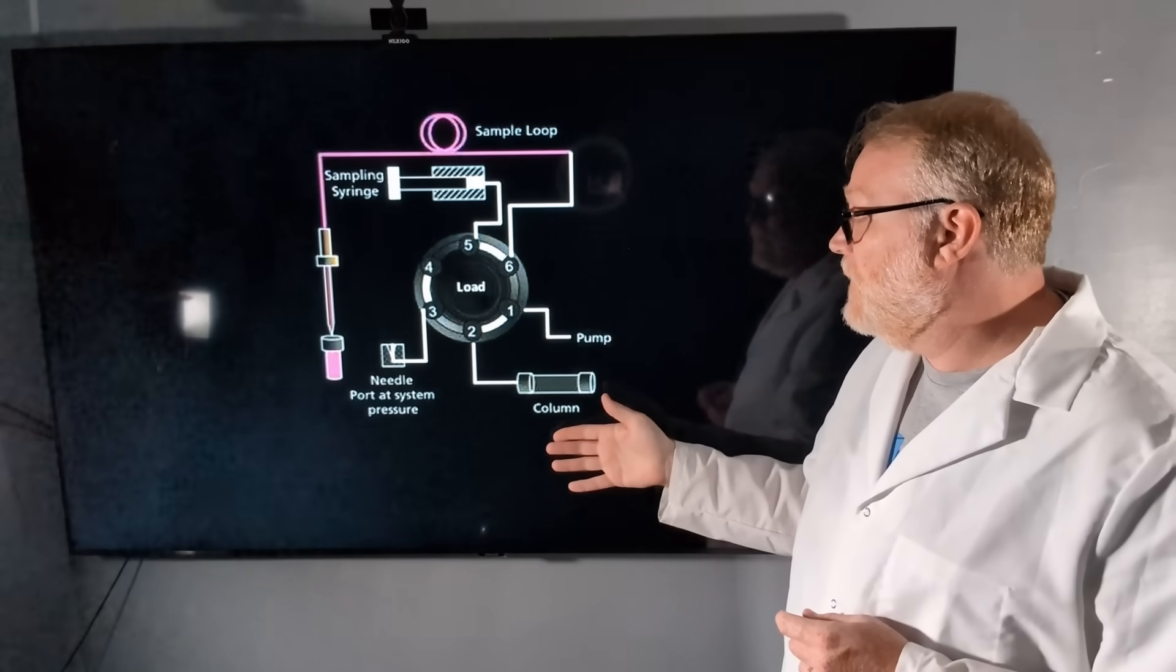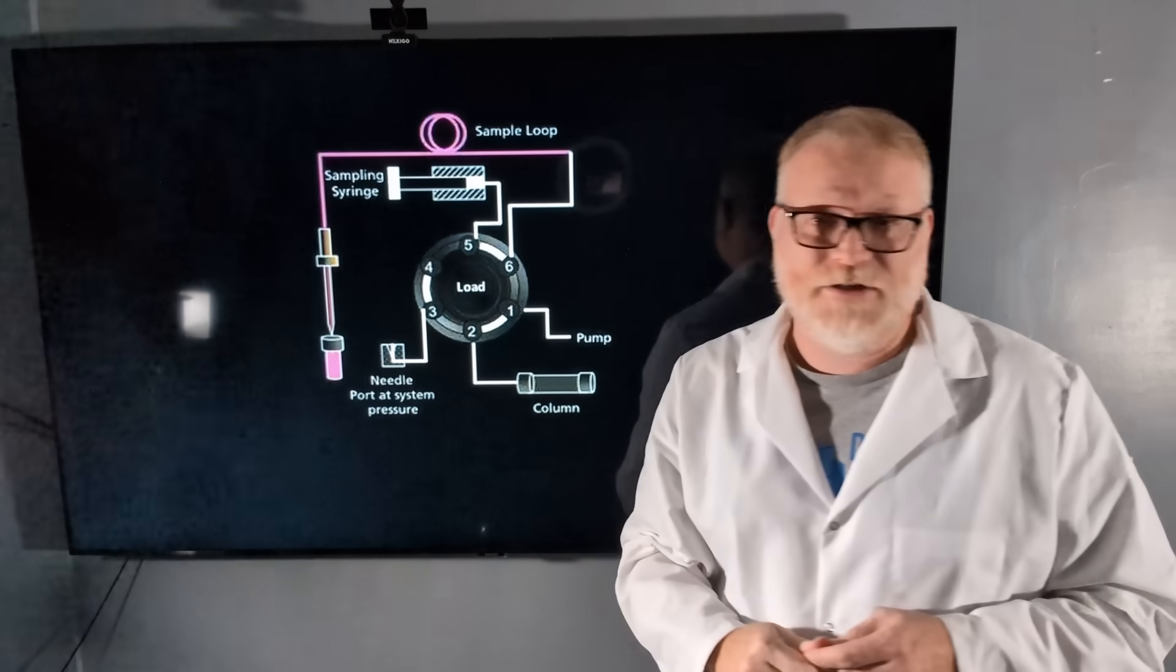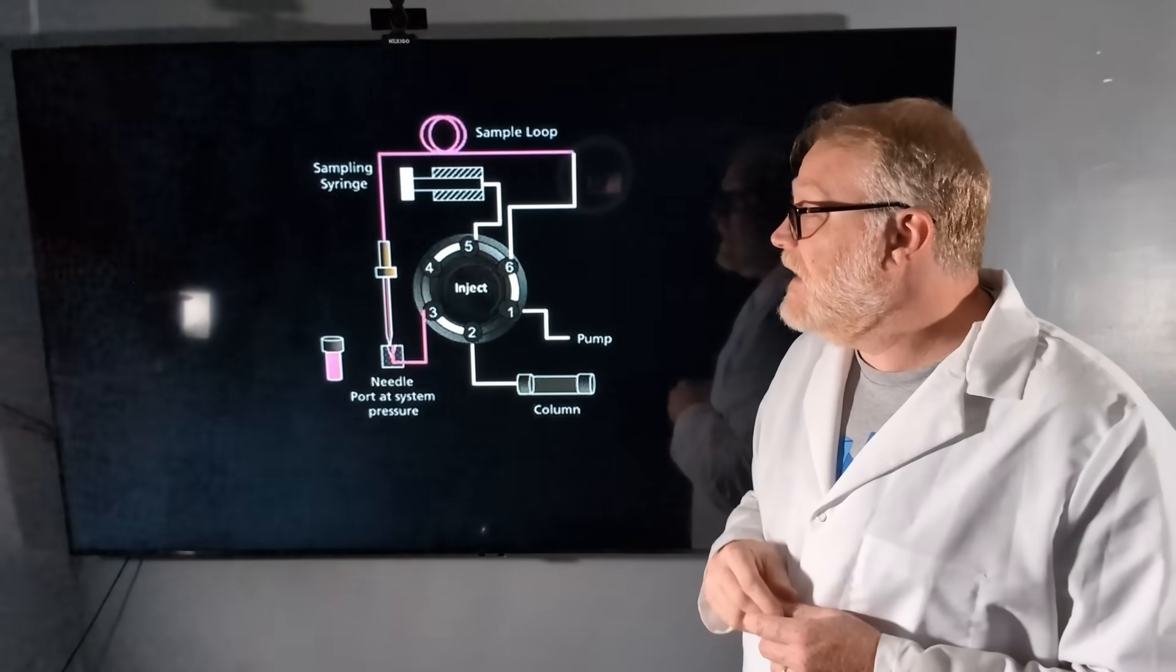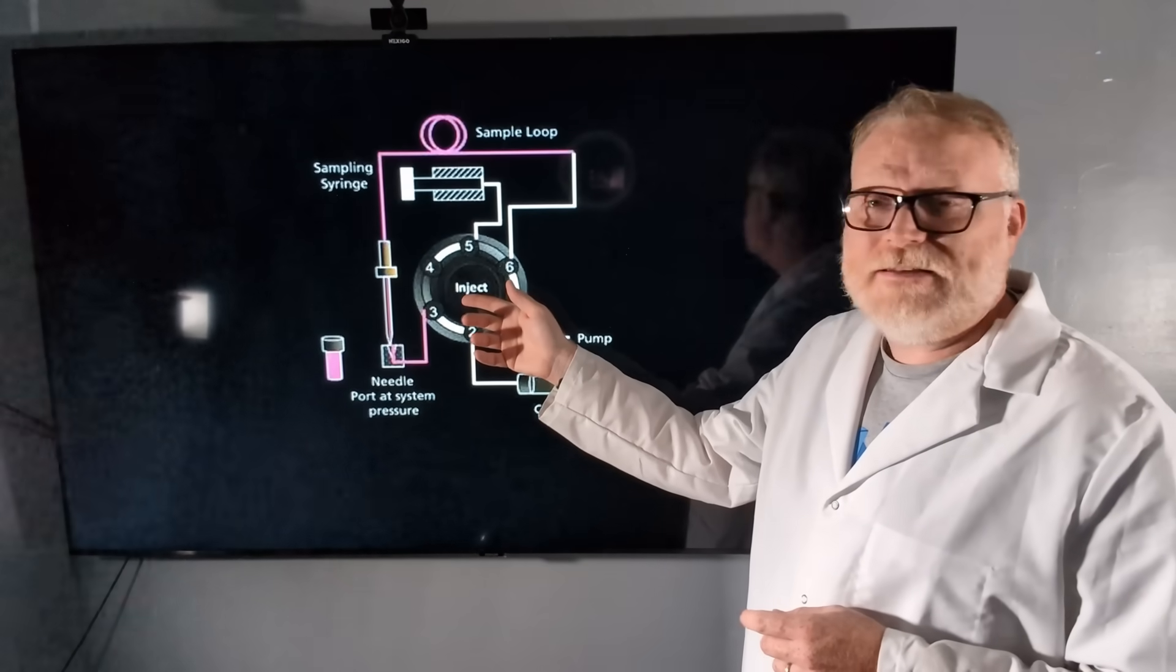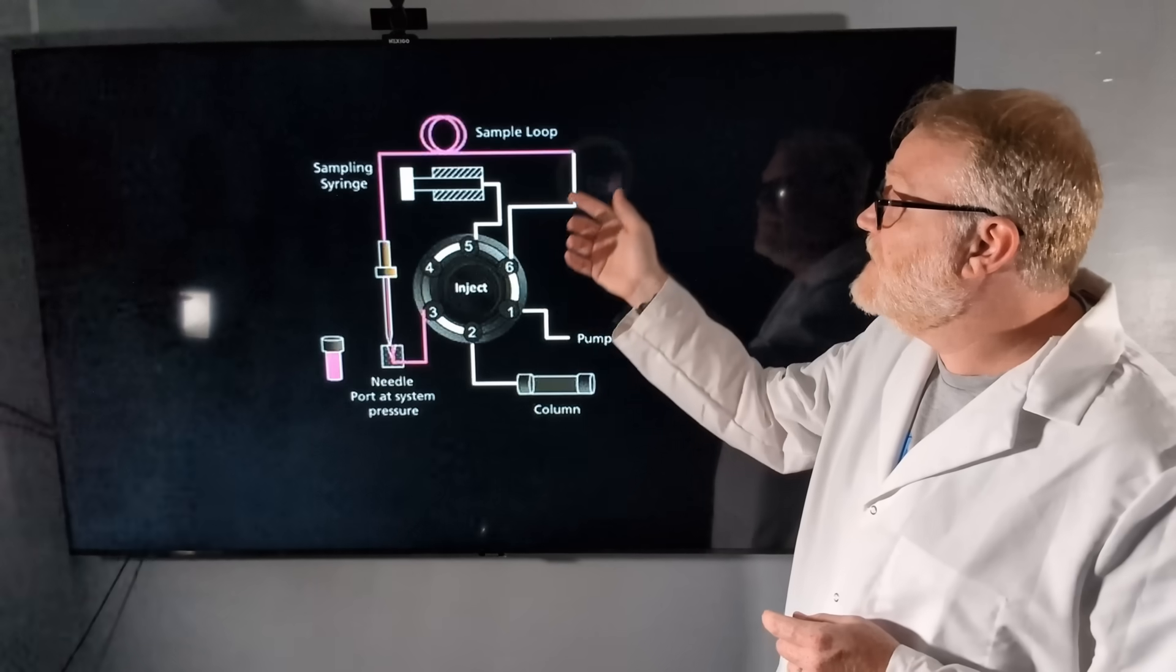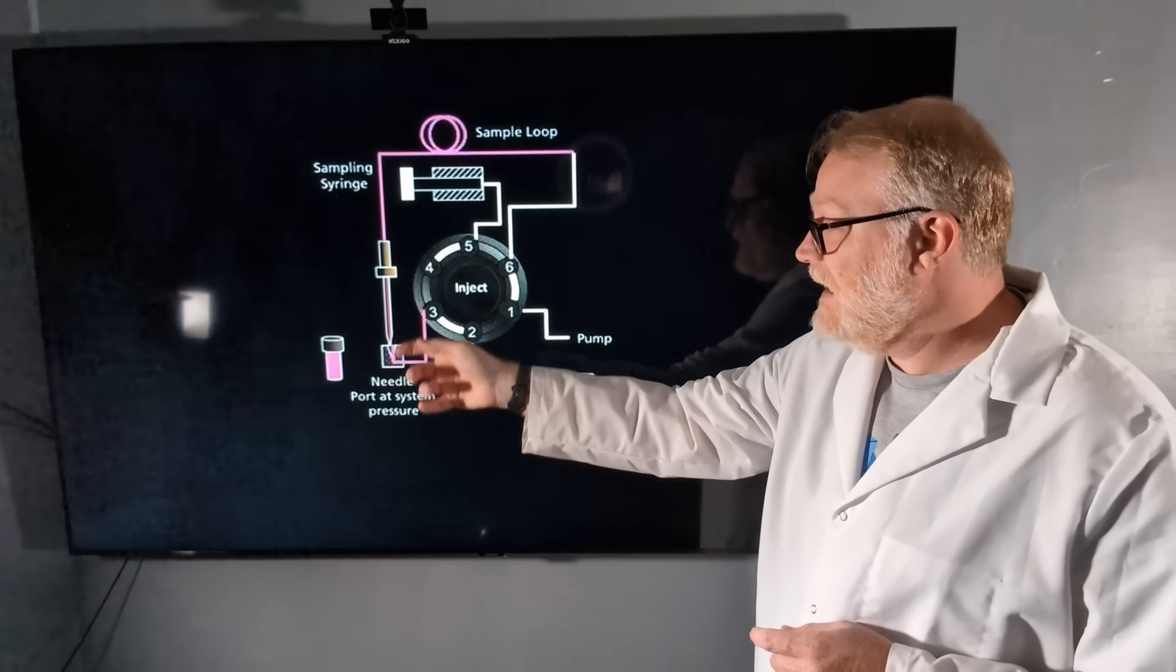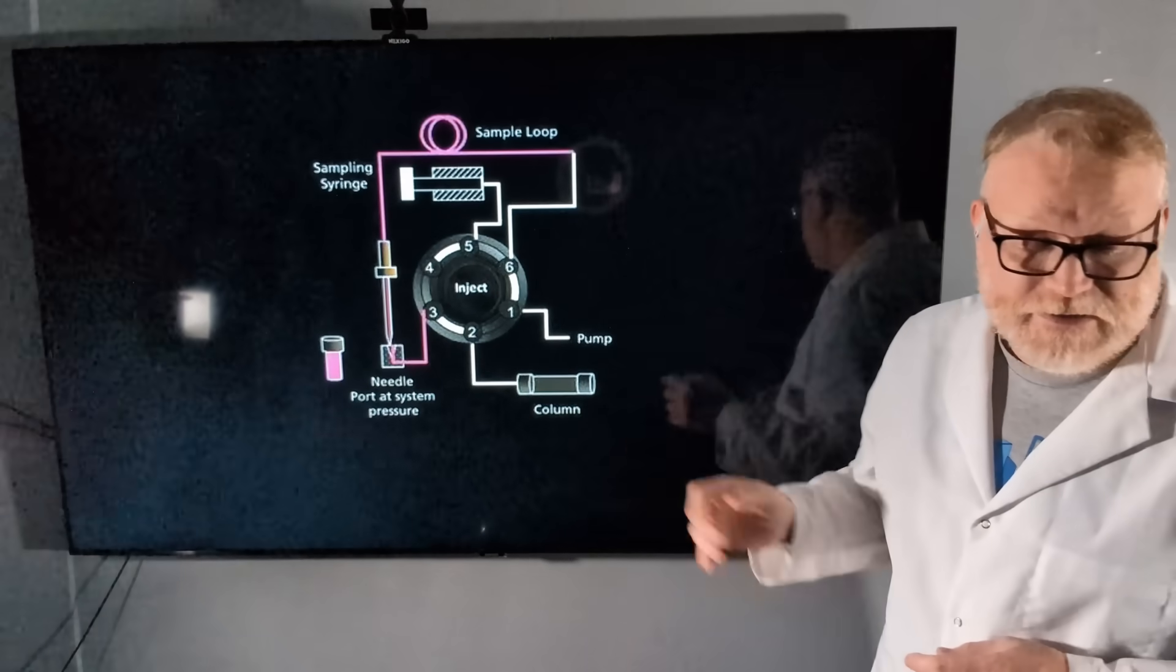We're in the load position. We've got a pump and a column. Now we have a high-pressure needle seat. That needle is going to then move into the high-pressure needle seat. The valve is going to move to inject. Now our pump is connected to our sample loop, which is now connected into that needle and needle seat, and then into our column to our detector.